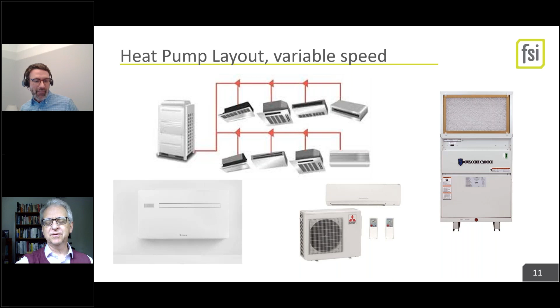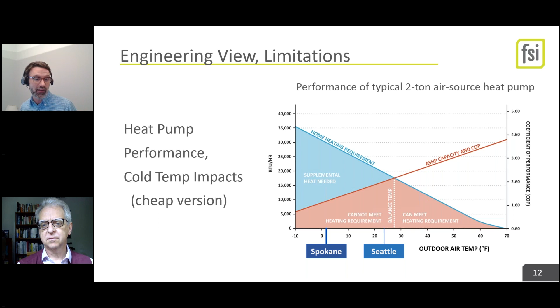So this is old single speed compressors, and they had temperature issues. When you got down below 20 or 25 degrees, you hit this heat balance, and you needed electric resistance backup to make up the heat. And of course, you need more heat the colder it gets, which is kind of a pisser. Even with our really well insulated buildings, and the code now, a code minimum building, is pretty good insulation. It still needs more heat the colder it gets. So single speed options, this is the drawback, and then you need a big electric service. But go to the next slide.